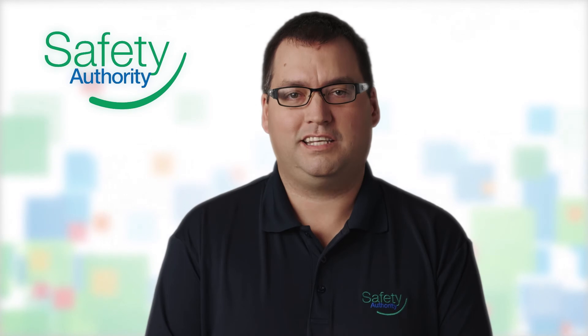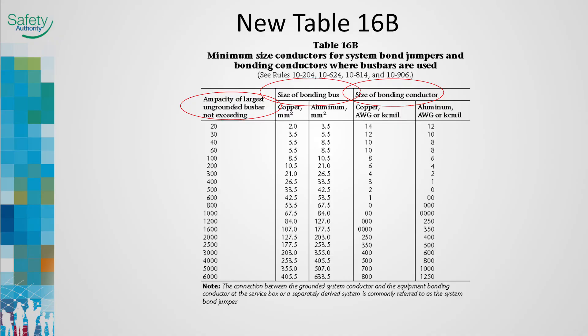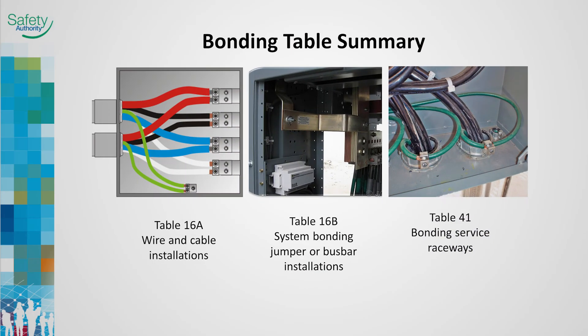Table 16B provides the minimum size bonding conductor for use as a system bonding jumper. Table 16B also provides the minimum size bonding conductor required when bus bar is used as the wiring method. The ampacity of the bus bar installation must be known before selecting a corresponding bonding conductor. The table is further divided into columns when using the bus bar or bonding wire. This slide illustrates the correct table to be used for the installations depicted.